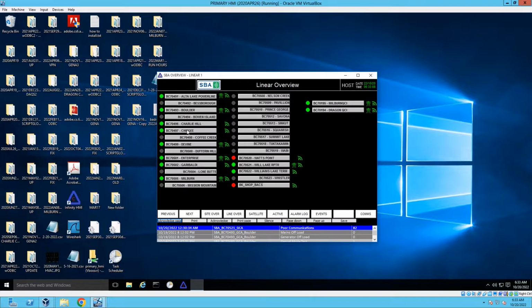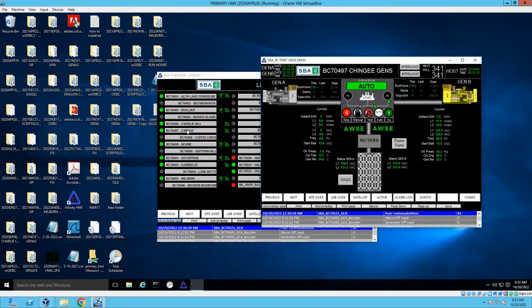This is a screen we developed for a prime power site. It includes dual generators, functioning as dual mutual standby. There is no utility power at this site, so when one generator is running, the other is on hot standby, ready to take the load in the event of a failure.